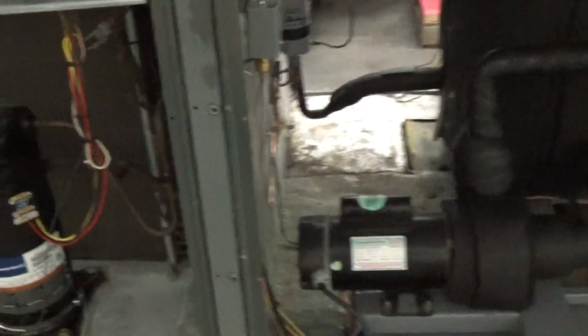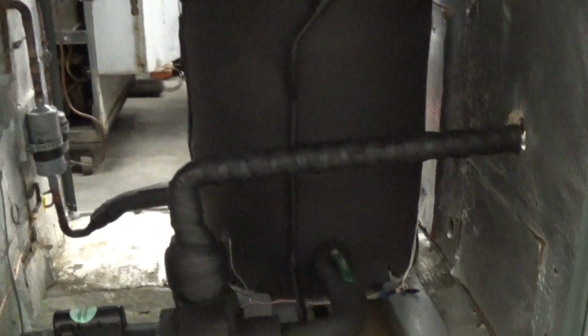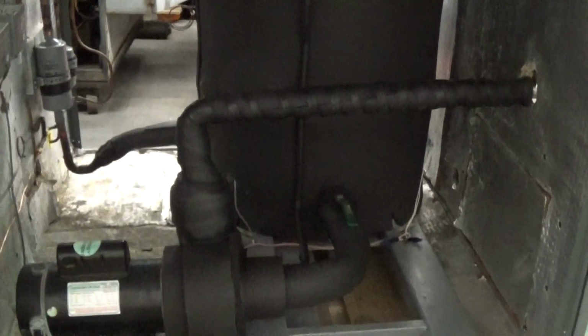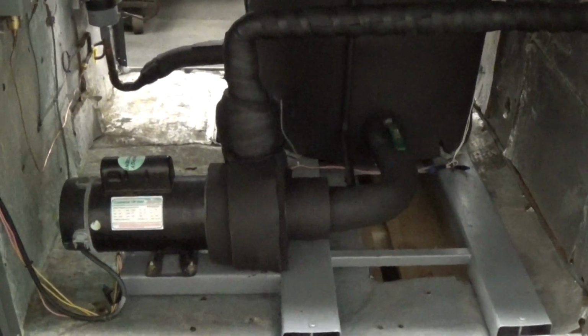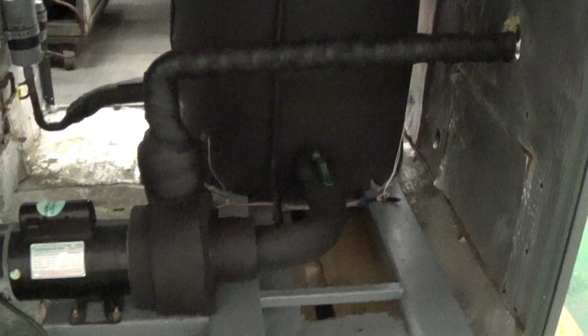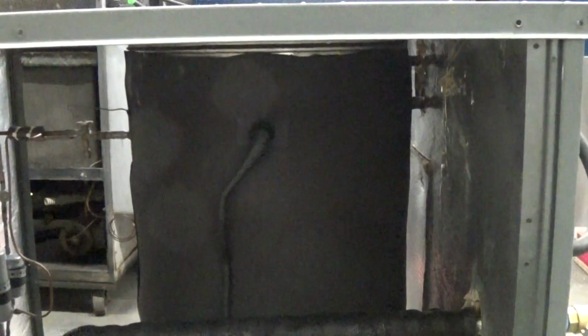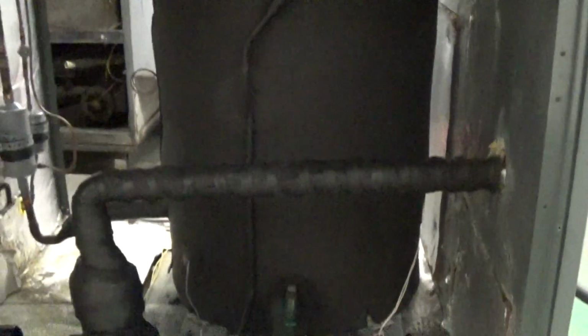So what we've done for this low temperature application is we've actually removed the tank, put a thicker insulation on the sides and on the bottom, reinstalled the tank, and we actually added additional insulation to the glycol lines. And we actually put a shutoff here also. So this is your suction drawing off the glycol reservoir, and then that just comes out, going out to your glycol loop. We have this little loop set up here for our testing, and we have that whole reservoir, which is about 55 gallons, full with a 40% concentration.